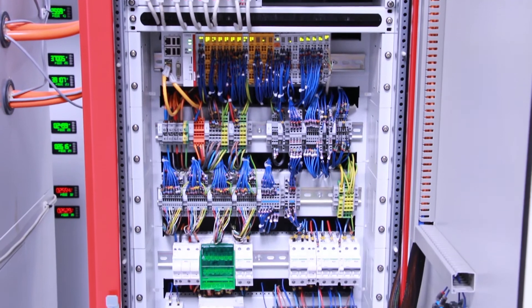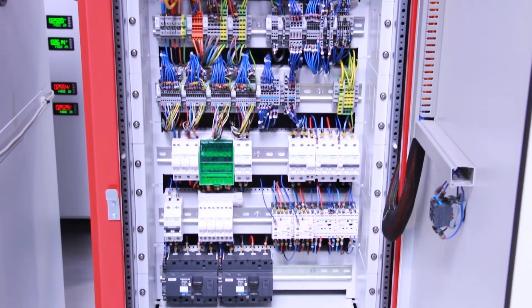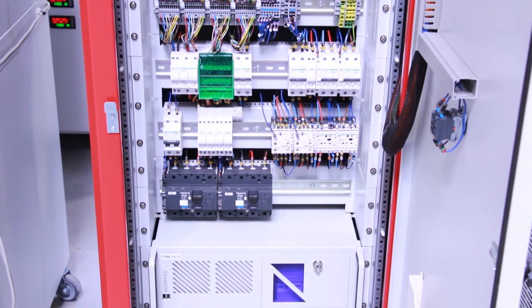In addition to the safety PLCs and the emergency stop buttons, we are monitoring the smoke. We have an infrared flame detector and we are monitoring the temperature. We are also monitoring the levels of HC and CO inside the chamber. Once a fire is detected, the first thing that happens is the injection of argonite inert gas. After that, we fill up the chamber with water. The third and last step is to collect the wastewater after the fire is finally out.